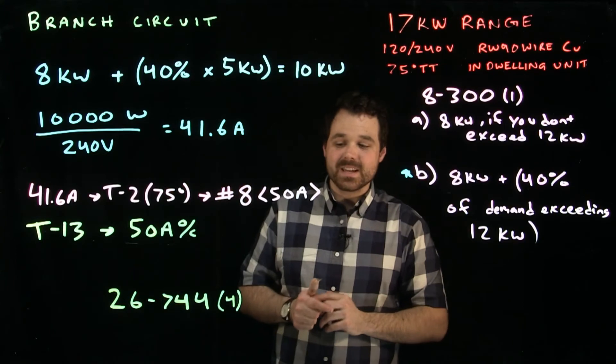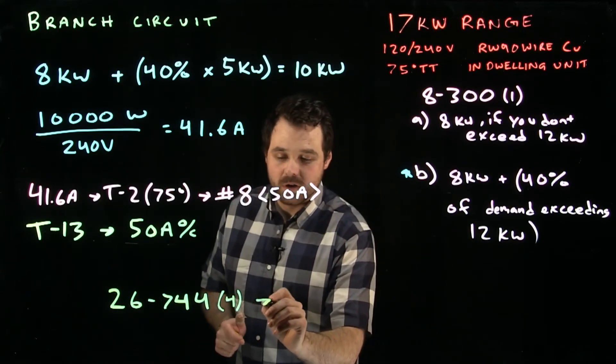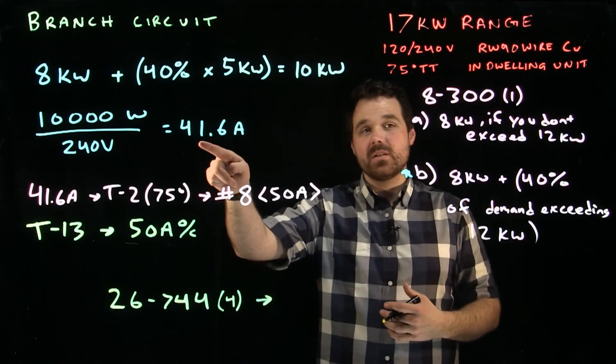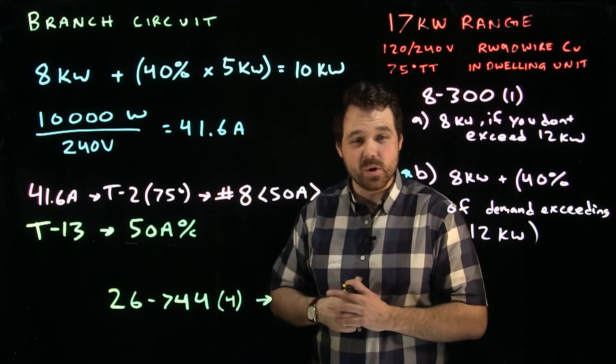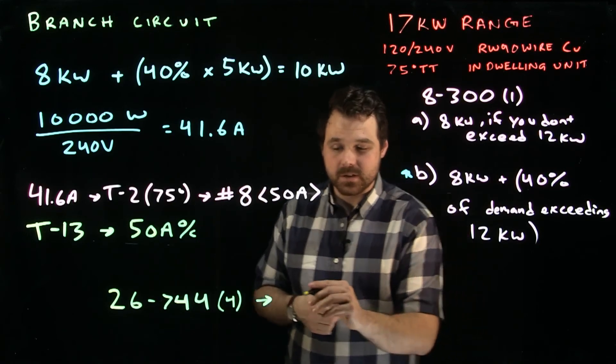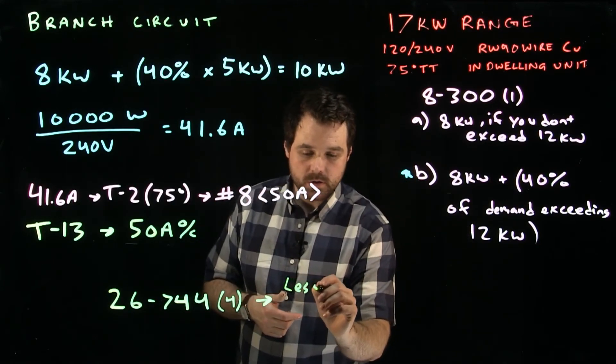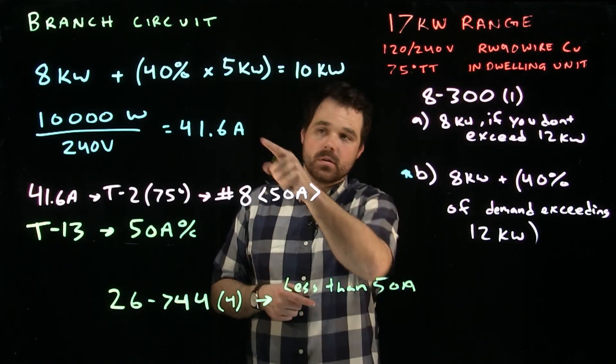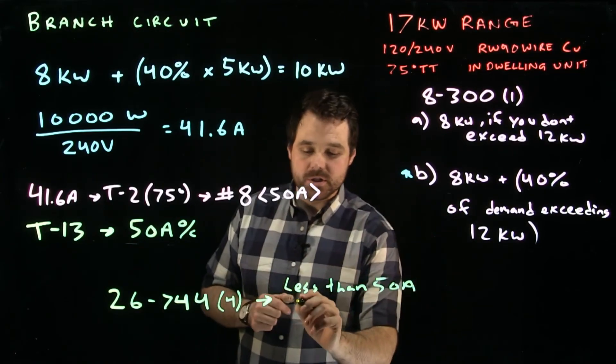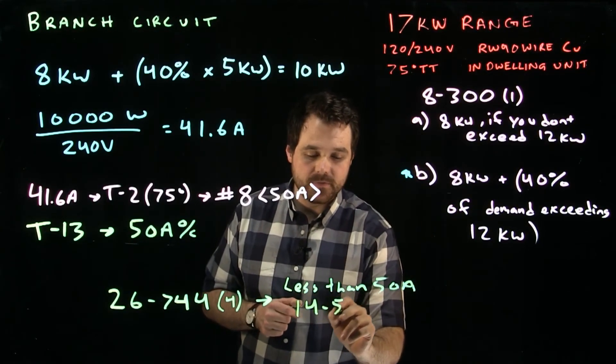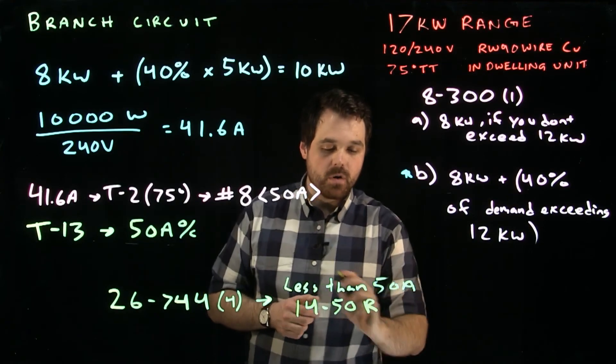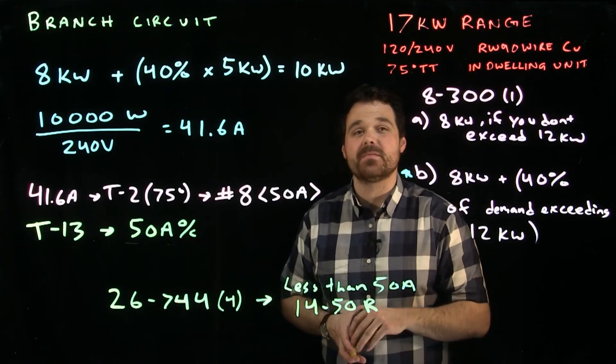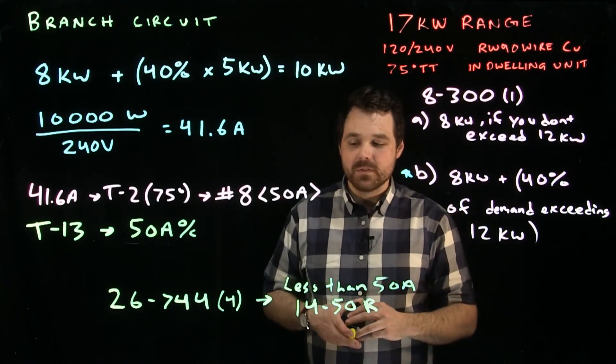Basically, 26-744 sub-rule 4 tells us if your range, your calculated load of your range, 41.6 is our calculated load. If your calculated load is less than 50 amps, that would mean we would have to put it onto a 14-50R. We have to put it onto a specific type of receptacle, just so that every house has the same type of plug or receptacle for their range.